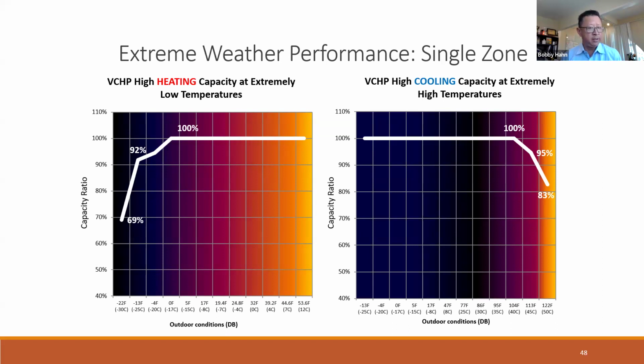So that's the main difference, is that refrigerant's getting flashed into the compressor to run harder, but run smoother at the same time, and have extremely good efficiencies when it comes to heating and low temperatures. So there you're going to see an example, 0 degrees, 100%. I think we're good in California for that. And on the right-hand side, you can see, and this application is going to be about 104 outside at 100%. So a lot of these, we'll call them, there's certain high temperature rated equipment, and I can say most manufacturers have something very similar to this type of performance.